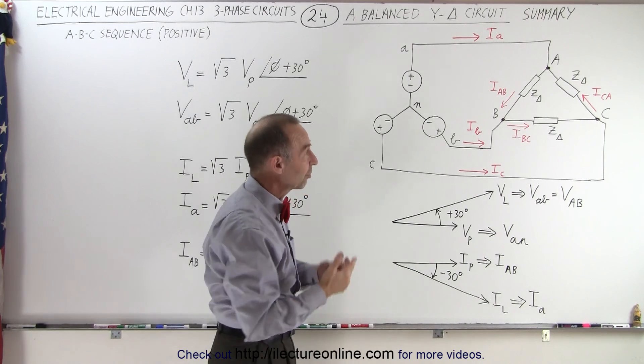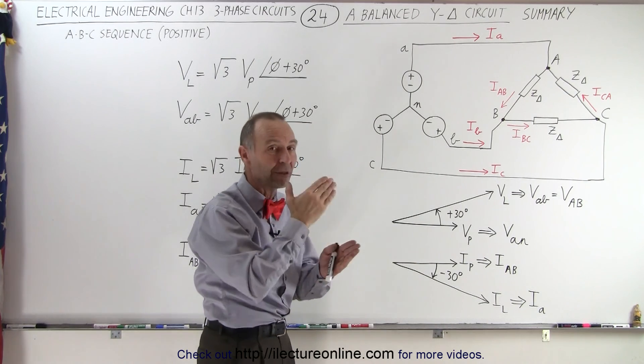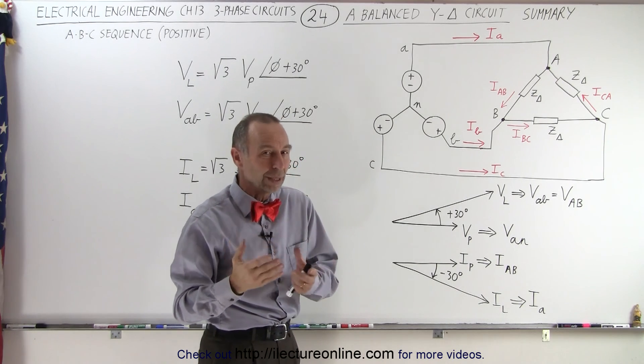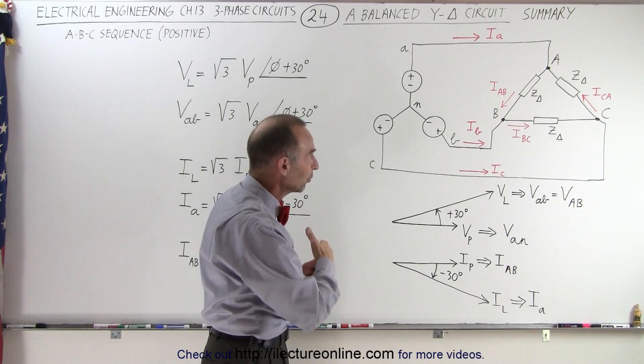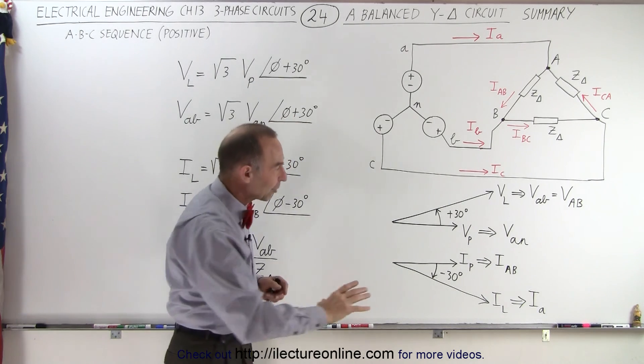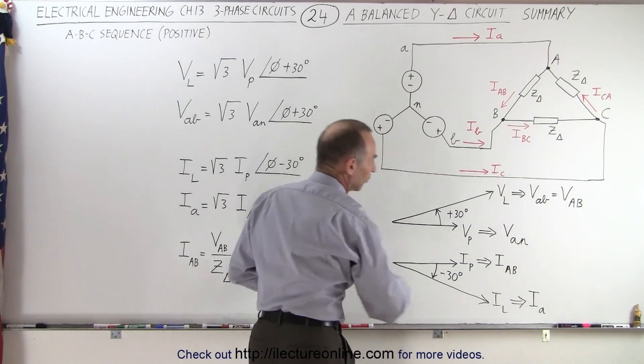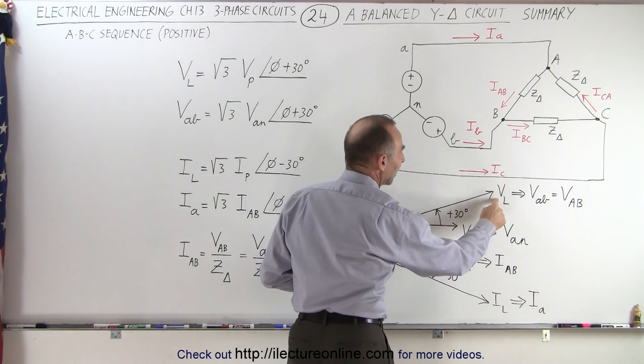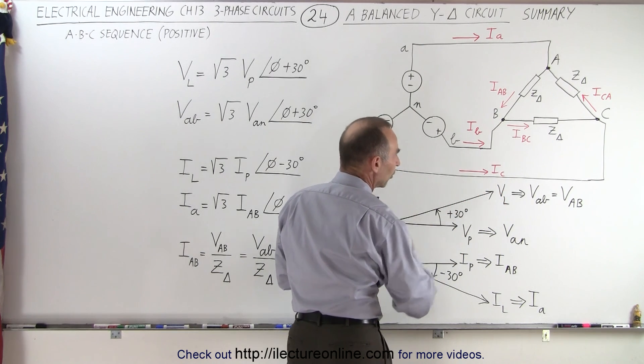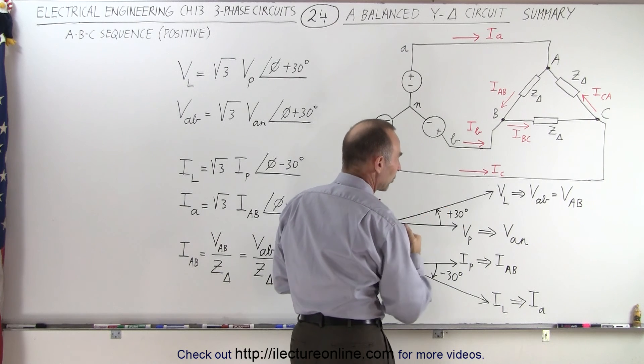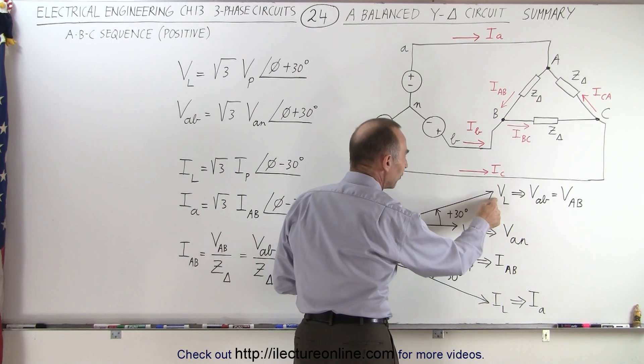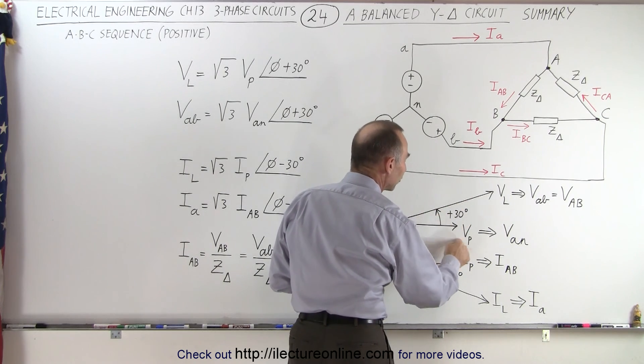We need to realize that there's a difference between the magnitude of the line currents and the phase currents, and between the line voltages and the phase voltages. There's also a difference in the phase angle between the line currents and the phase currents, and the line voltages and the phase voltages. Here we have a graphical representation of those differences. The line voltage is larger in magnitude than the phase voltage by a factor of the square root of 3, and the line voltage leads the phase voltage by 30 degrees.